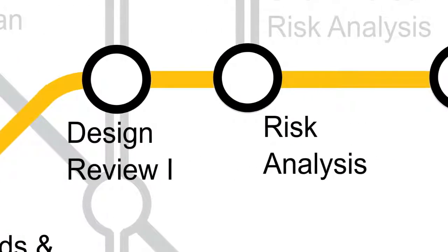Risk analysis has 2 parts. Firstly, identifying potential risks for the design, manufacture, assembly, distribution, use and disposal of the product. The second part is evaluating each of these against the hazards and harms I mentioned just now. You'll prioritise these risks based on their probability and the severity of the harm that could result. This allows you to focus on addressing the most important ones first.